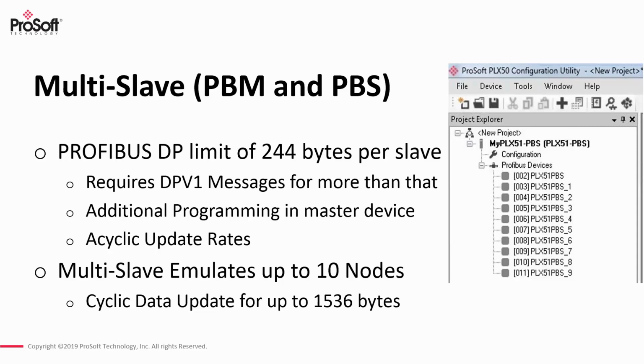And so this allows you to transfer up to the full support of 1,536 bytes of data, all as cyclic I/O data, without any additional DPV1 messages or additional programming in a master device.